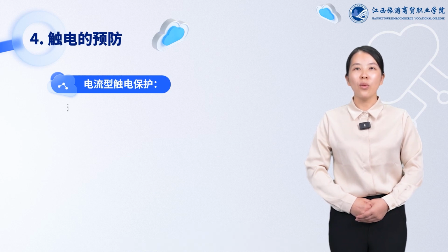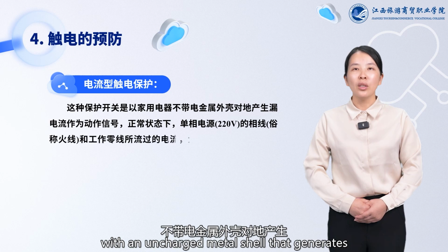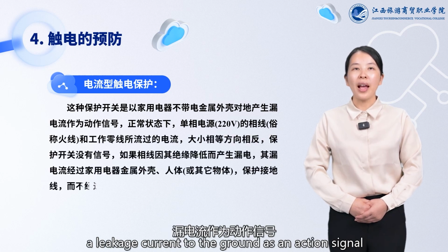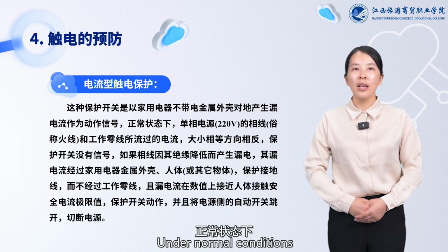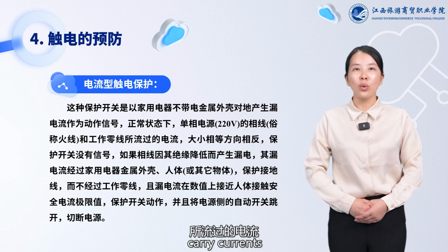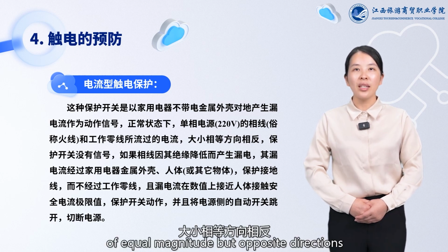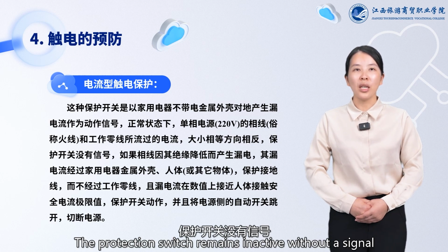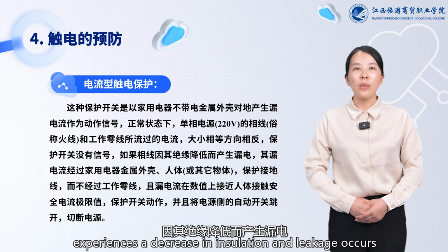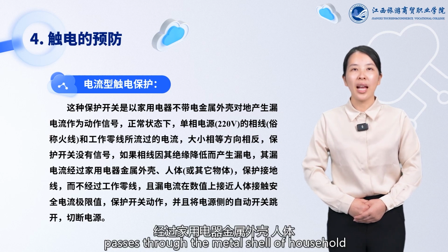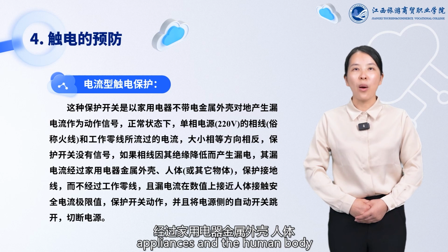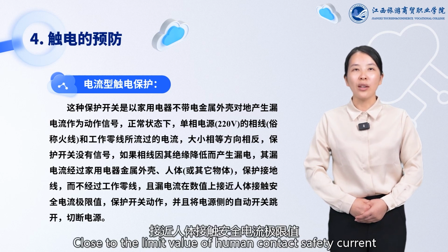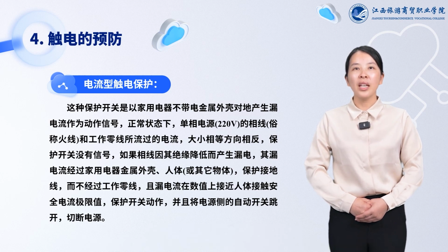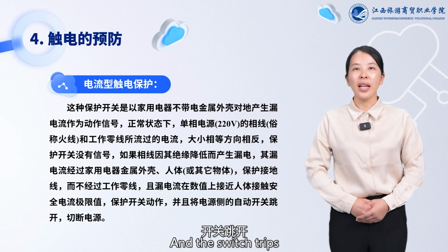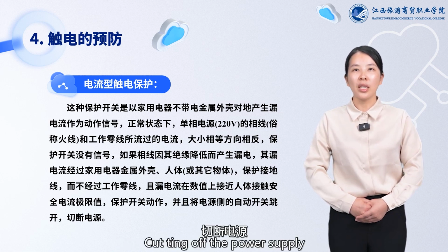Current-type electric shock protection is based on household appliances with an uncharged metal shell that generates a leakage current to the ground as an action signal. Under normal conditions, fire line and working zero line carry currents of equal magnitude but opposite directions. The protection switch remains inactive without a signal. However, if the phase line experiences a decrease in insulation and leakage occurs, the leakage current passes through the metal shell of household appliances and the human body, and it reaches a numerical value close to the limit value of human contact safety current. As a result, the protection switch activates and the switch trips, cutting off the power supply.